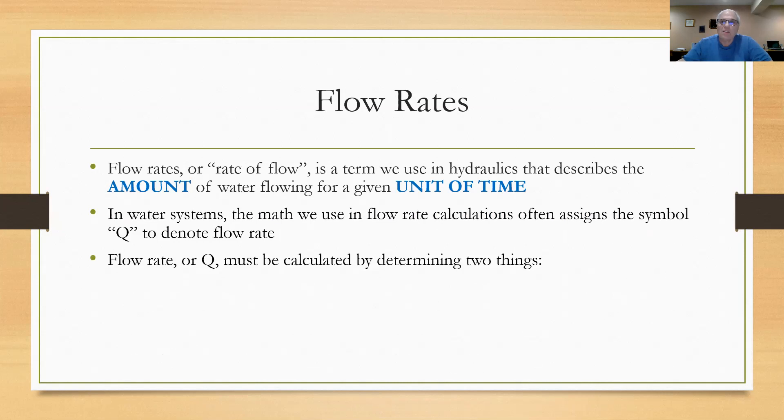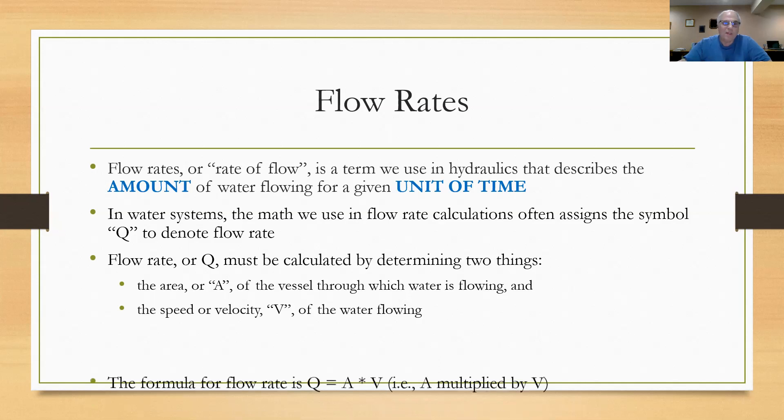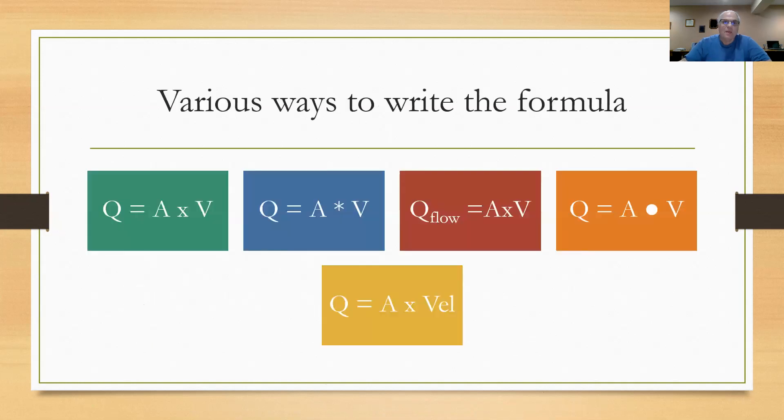So flow rate or Q has to be calculated by determining those two things. We have to get the area of the vessel that's carrying the water - it's either going to be a pipe or an open channel in a water plant. And we also have to know the speed or the velocity of the water that's flowing through that pipe or channel. So the formula that we use is Q equals A times V, the area multiplied by the velocity. They often write these formulas in different ways, but if you see any of these variations, it's really all the same thing: flow rate equals area times velocity.